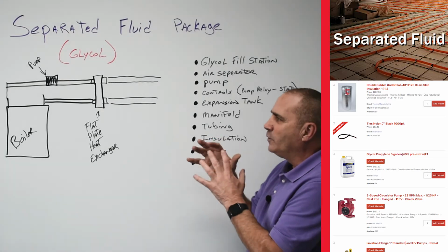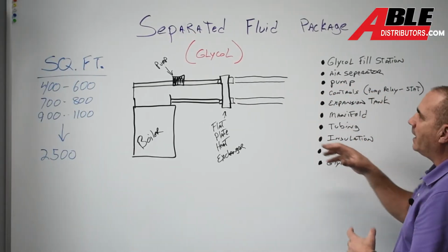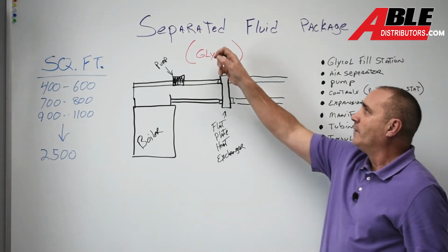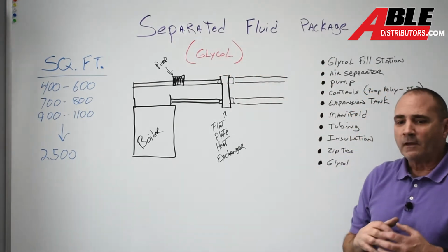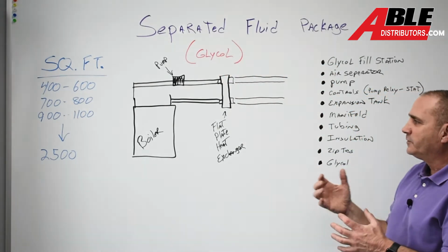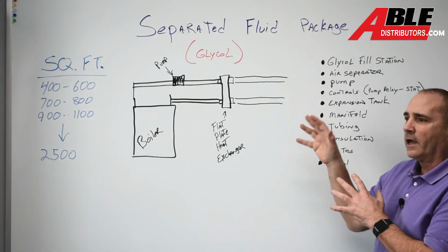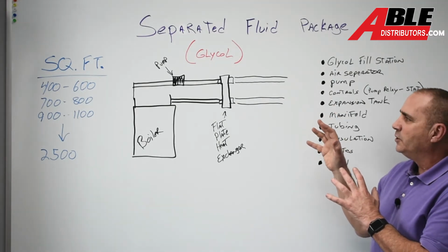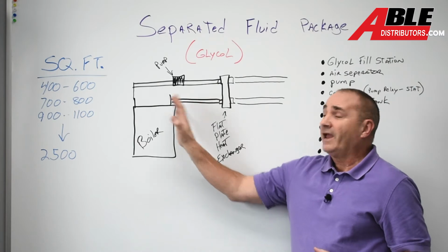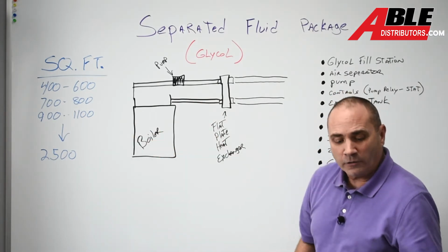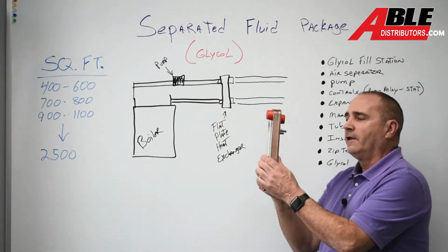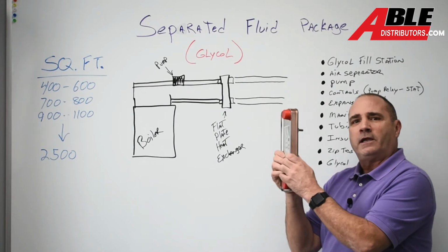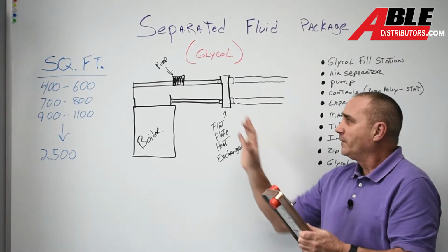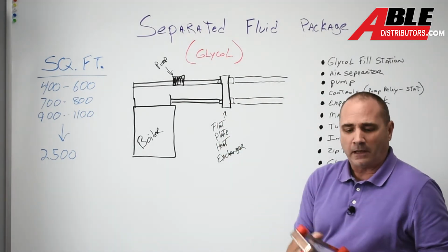If you are looking at this and you're in the wrong section, we have a regular radiant floor system section. If you were going to go glycol and you were not going to have a boiler do anything but this, all you need to do at this point is say, okay, I don't need the flat plate heat exchanger because the whole system, including the fluid in the boiler, is going to be glycol.